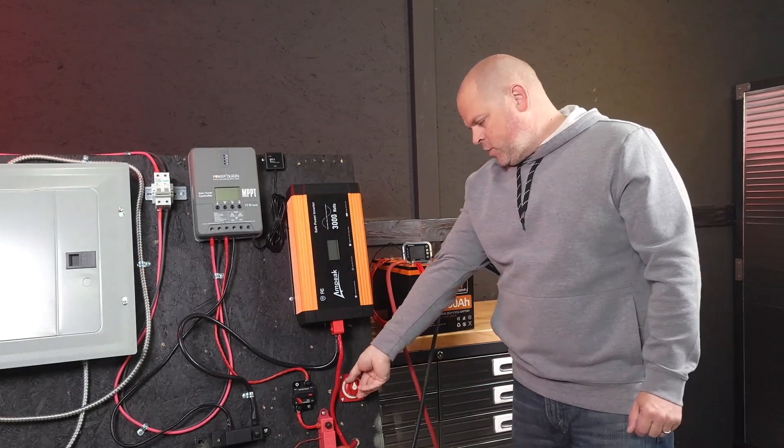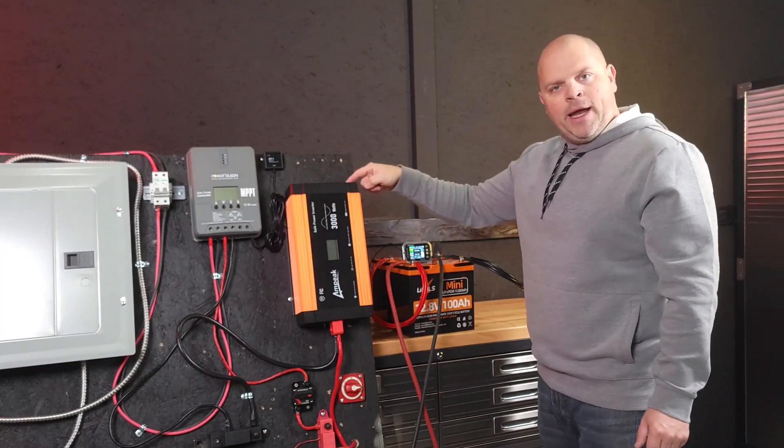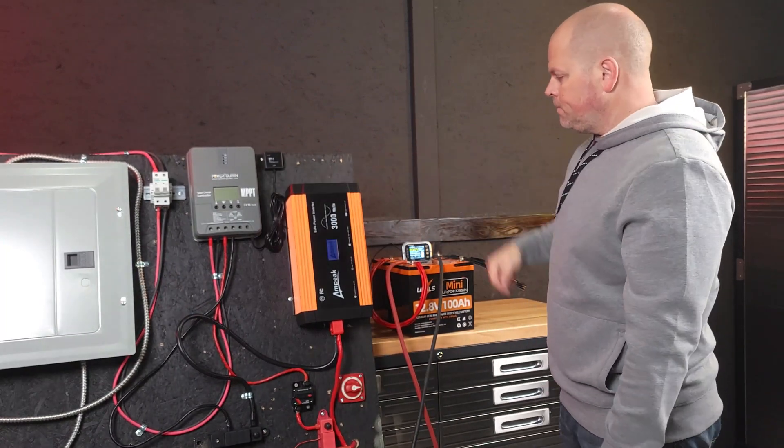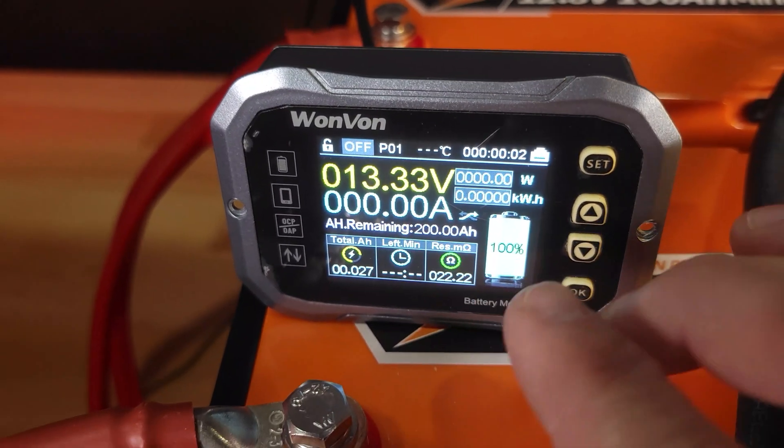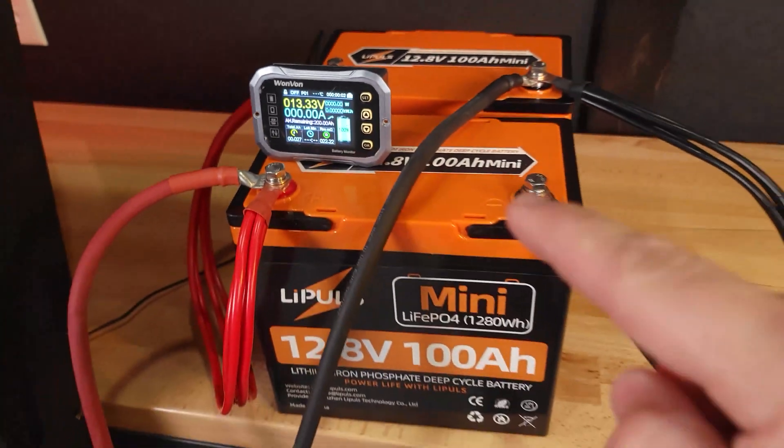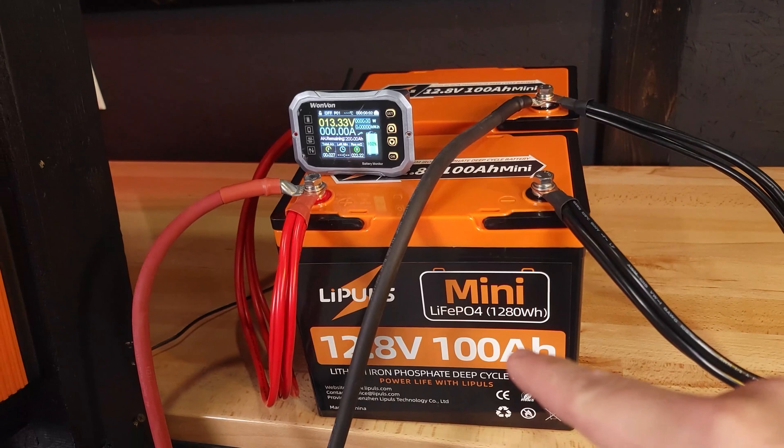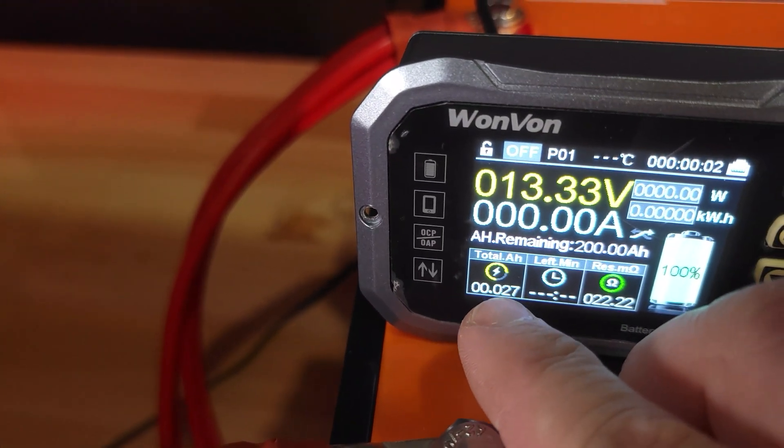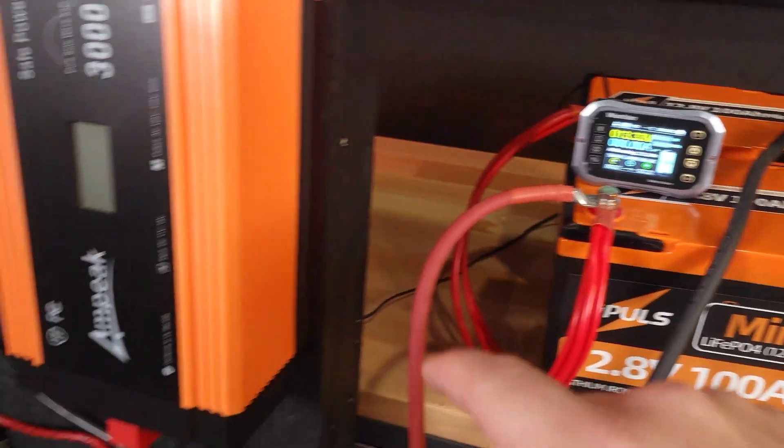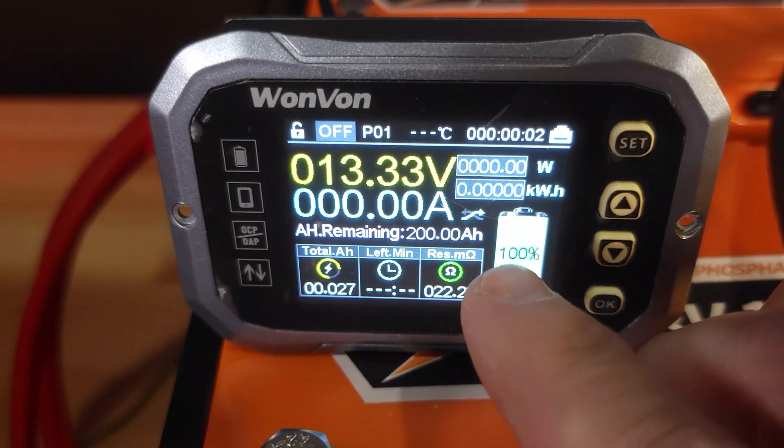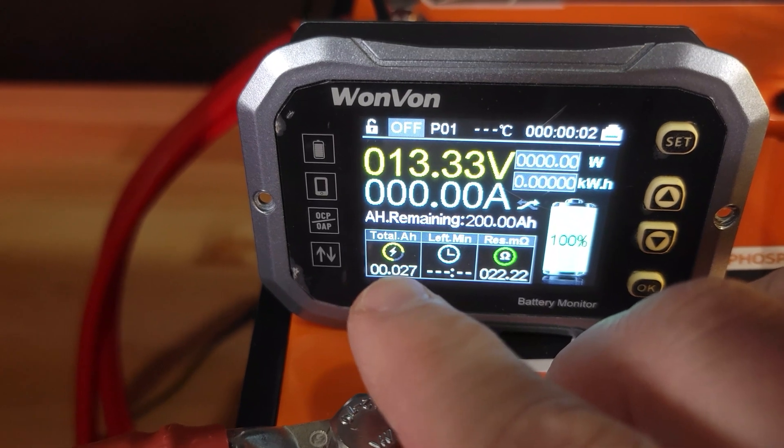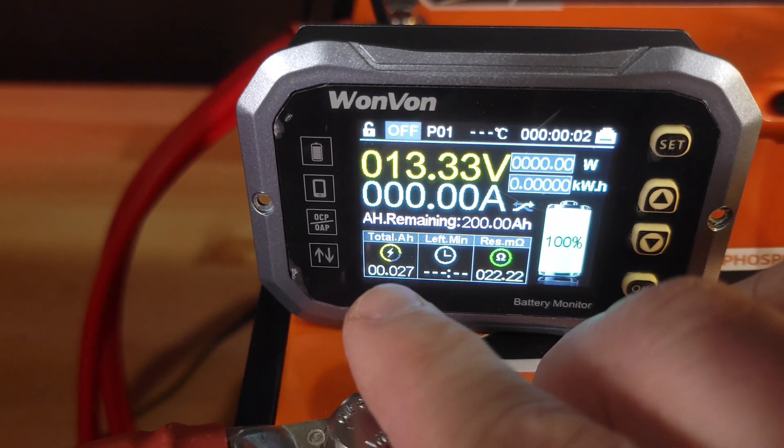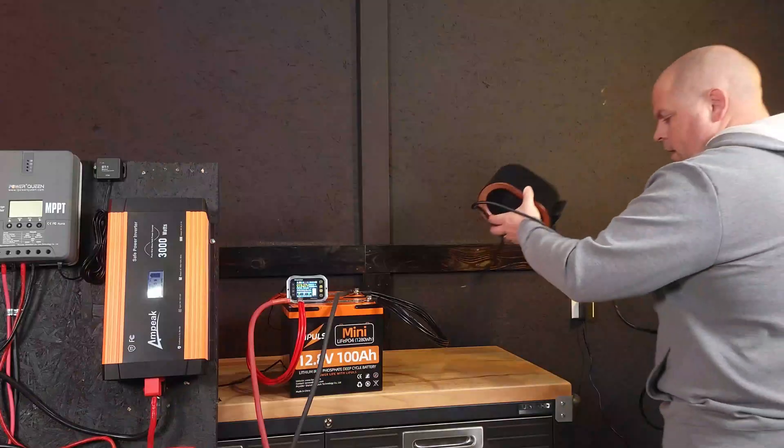So we've got to flip this switch, turns on the shunt, and then we'll turn on our inverter. Let me explain a little bit about the display. For everyone that might not know this, the remaining amp hours is 200 amp hours. That's because we have two 100 amp hours connected in parallel. We've used a little bit of power out of these batteries because when we turned on the inverter, it used a little bit, but we're still sitting at 100%. This number that we're looking for here should match the 200 amp hours or better to pass the capacity test.